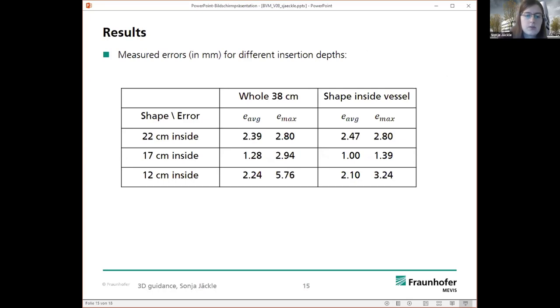And here you can see the errors for all three depths, insertion depths. In the middle, you see the whole 38 centimeter, and on the right side, you see the shape inside the vessel. So, for the whole 38 centimeter shapes, we obtained average errors from around 1 up to 2 millimeters, and maximum errors from around 3 up to 6 millimeters.